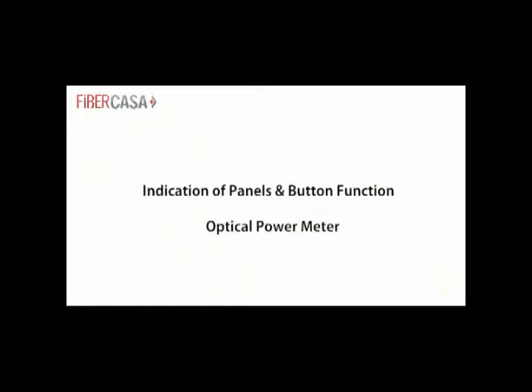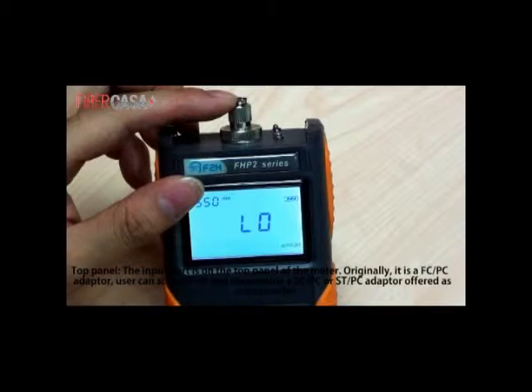Indication of panel and button function - Optical Power Meter. Top panel. The input port is on the top panel of the meter. Originally it is a FC-PC adapter. Users can screw it off and reassemble a SC-PC or ST-PC adapter offered as an accessory.